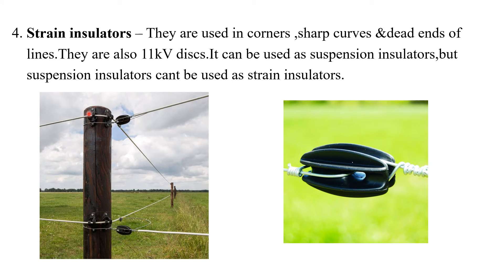The fourth type of insulator is the strain insulator. They are used at corners, sharp curves, or dead ends of the lines. An important point is that strain insulators can be used as suspension insulators, but suspension insulators cannot be used as strain insulators. That is the important comparison between suspension and strain insulators.